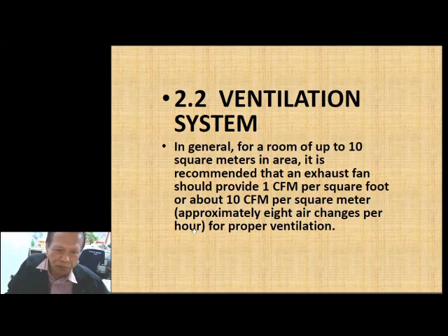So, here I got some data where you could easily determine these values. But you'll take note that there is a minimum value from 3 to 10, no? So, let's say, for example, let's have a sample here. Let's get a classroom. So, classroom, pwedeng from 4 minimum to 6. Okay? 4 to 6. So, CFM is equal to room volume divided by the minutes per change. And then, room volume is equal to length times width times height of the room. So, whatever is the volume, room volume, makukuha mo dyan, no? Okay. So, classroom, 4 to 6, di ba? Or, projection room, 2 to 7.